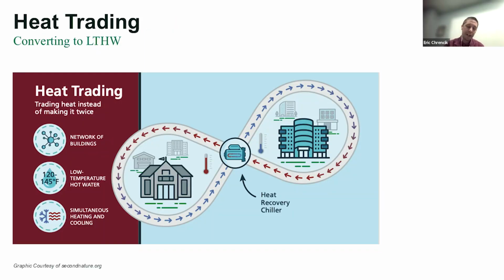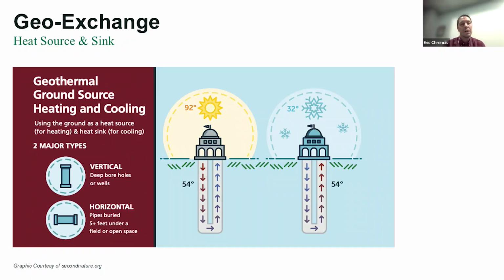And as we talk about trading heat, it's some more broader concepts. Part of what we were looking at and proposed was converting to hot water away from their steam system, with the idea that they could use heat recovery chillers, they could operate at lower water temperatures to have some reduced energy losses throughout their systems, and then really take advantage of simultaneous heating and cooling, which also paired with ground source heat exchange can give it a lot of flexibility in modes of operation and really hit hard on the electrification piece.